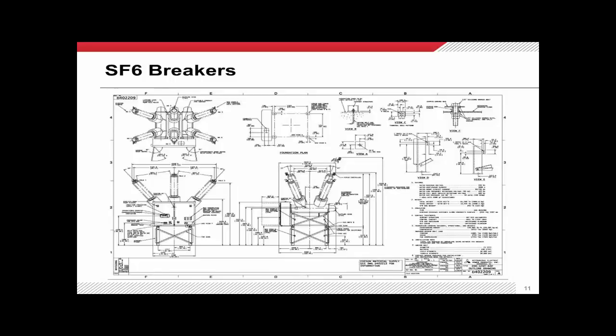On the top right is information you'll need to design your foundation, and a little information about where you can run conduits to get your control wiring out of the circuit breaker and into your raceway system, which will take it back to your control building. On the side is a face view of the breaker giving you good information about the physical dimensions. This drawing also shows the height of the bushing, the clear space needed above the circuit breaker to remove a bushing, and how much clear space is needed for maintenance on the interrupters.